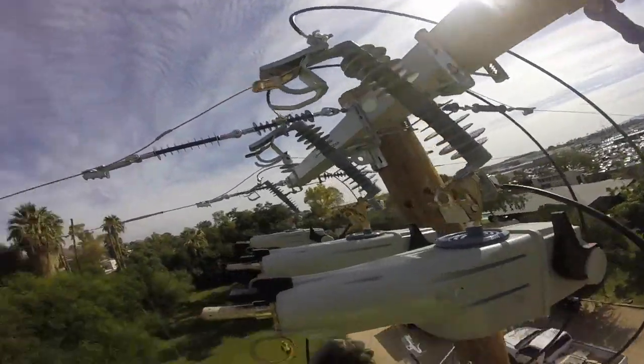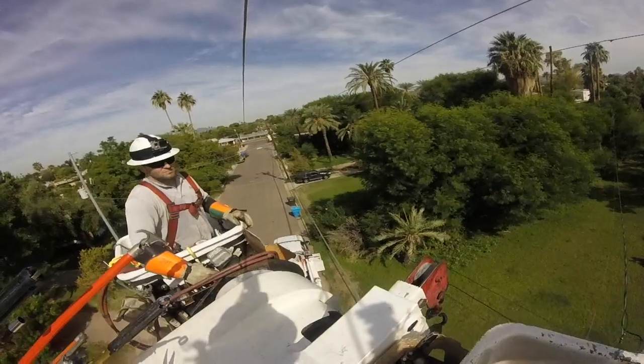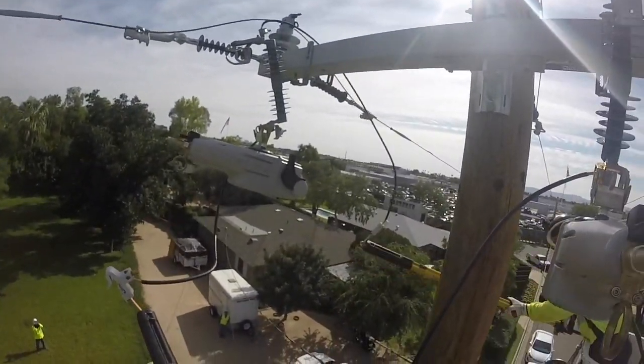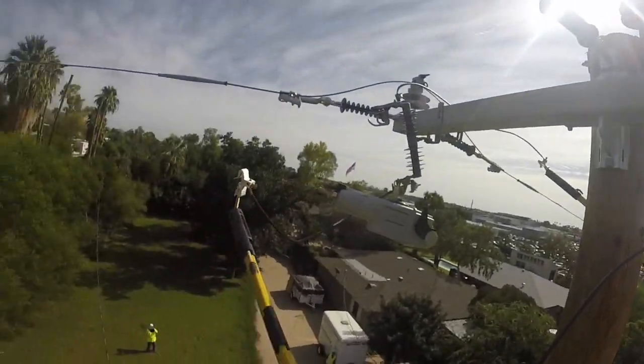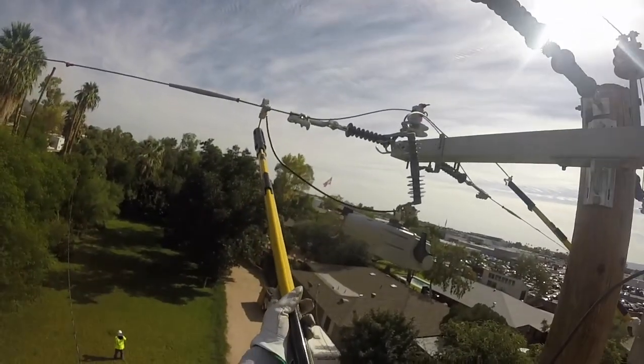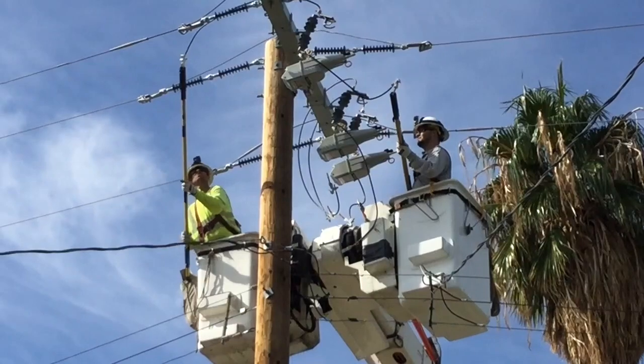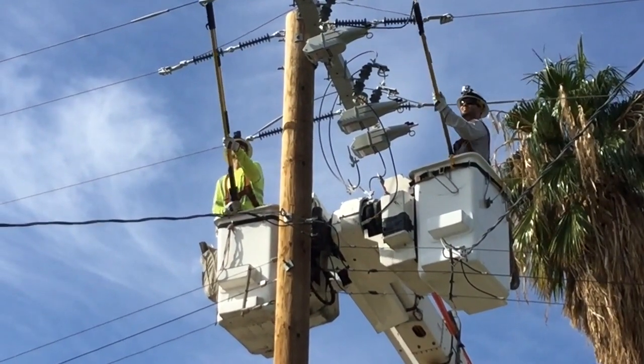He's going to hang the other two trip savers right next to it on the line and again verify good closing operation. Now, in order to complete the trip saver installation, they have to connect jumpers from both the bottom and top of the switch.